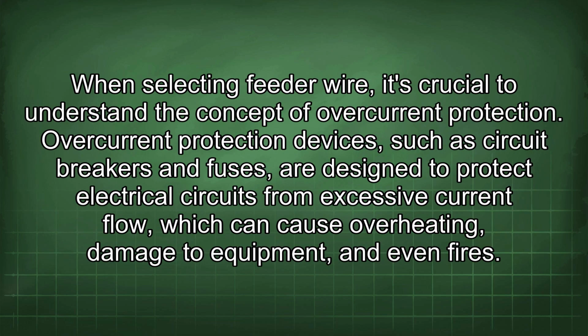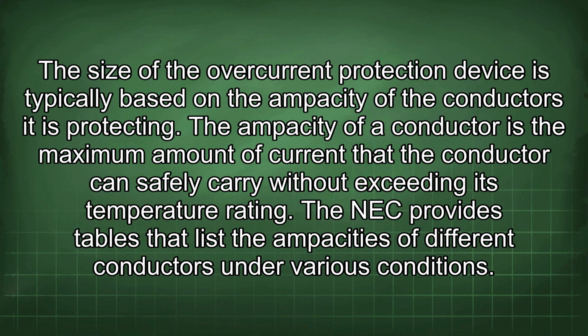When selecting feeder wire, it's crucial to understand the concept of overcurrent protection. Overcurrent protection devices, such as circuit breakers and fuses, are designed to protect electrical circuits from excessive current flow, which can cause overheating, damage to equipment, and even fires. The size of the overcurrent protection device is typically based on the ampacity of the conductors it is protecting. The ampacity of a conductor is the maximum amount of current that the conductor can safely carry without exceeding its temperature rating.